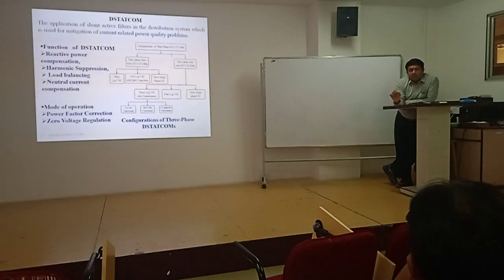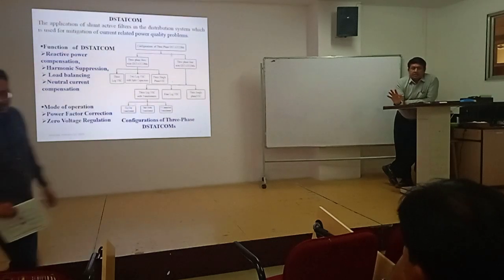a shunt active filter for compensation of reactive power. This is the reactive power. Reactive power is the primary objective. After that, the system should also work for harmonic compensation and unbalancing. If a 4-wire system is there, in that case, that one also works as neutral current compensation, in power factor correction as well as the ZVR mode.